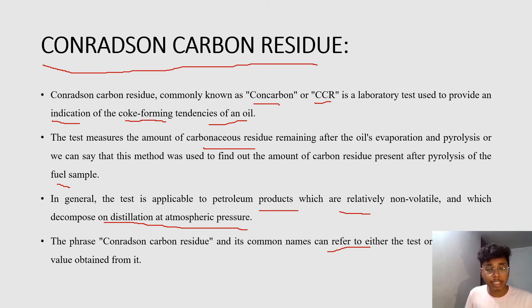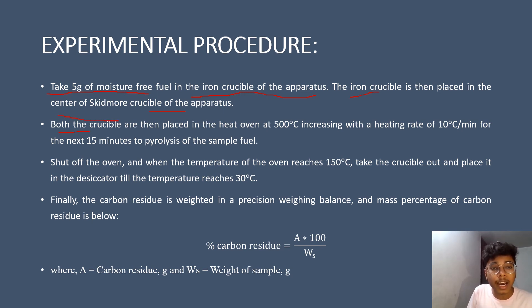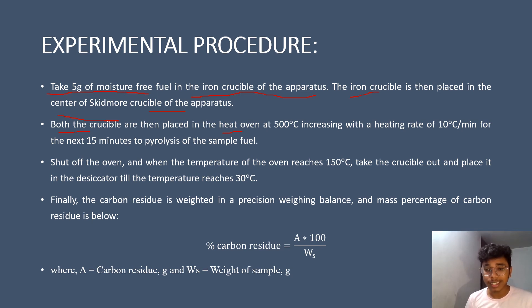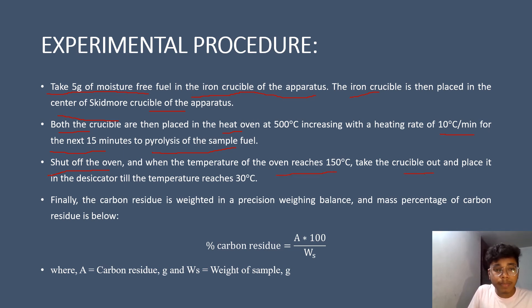For the experimental procedure: first, take 5 grams of moisture-free fuel in the iron crucible of the apparatus. Then place the iron crucible inside the center of the Skidmore crucible of the apparatus. Both crucibles are then placed in a heat oven initially at 500°C, and the temperature is increased by 10°C per minute for the next 15 minutes, during which pyrolysis of the sample is performed. After 15 minutes, shut off the oven, and when the temperature reaches 150°C, take the crucible out and place it in a desiccator to cool until the temperature reaches 30°C.